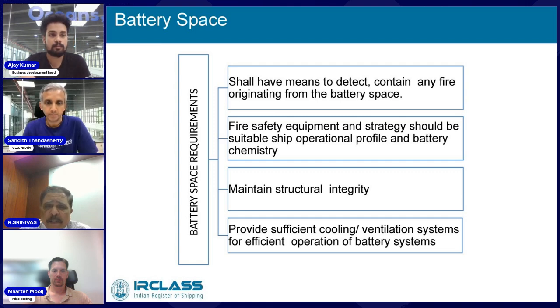And we should have proper fire safety equipment. Whatever fire equipment is designed for mitigating or extinguishing the fire has to be suitable for the chemistry. That's very important. It's not dogmatic that it must be water-based - it is very important that the manufacturer is consulted as to what kind of battery chemistry is there and which kind of extinguisher system is suitable for that.